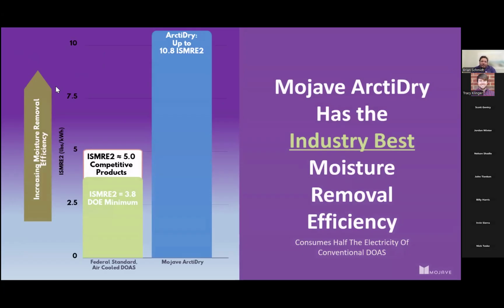Mojave is 10.8 without an ERV. So we are more than twice as energy efficient as the federal minimum with an ERV, and that is without us having an ERV. So when I say Mojave is the most energy efficient DOAS system on the market, this is proving it right here, the ISMRE2 value. So again, if you are looking at a project and would like to compare apples to apples, certainly you need to look at the ISMRE2 value, not necessarily the IEER values.